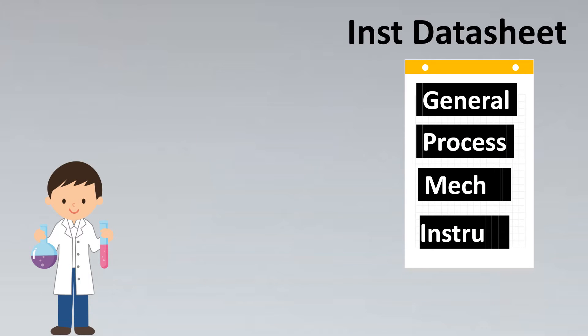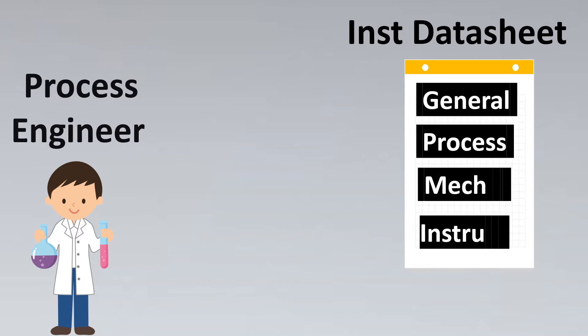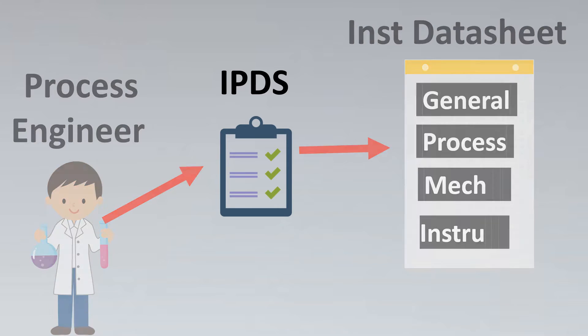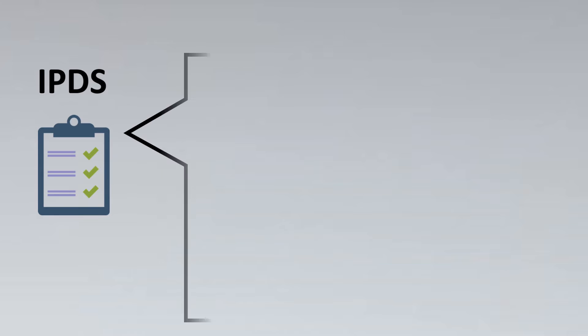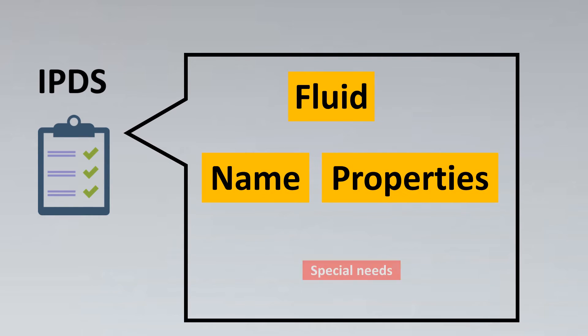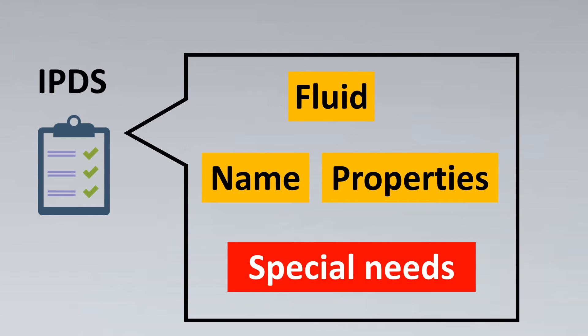The next step is to get the process data. For this, the process engineer would be very helpful. They prepare a document called IPDS — Instrument Process Data Sheet — and this is the basis to fill the process section of an instrument data sheet. IPDS basically contains the fluid, its name, properties, and some special needs — for example, if it's corrosive, toxic, erosive, etc.